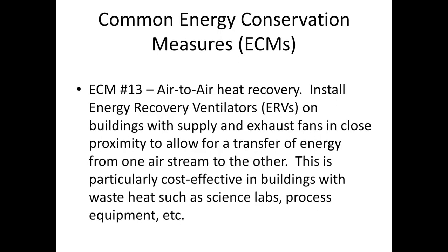So this is really installing energy recovery ventilators in a lot of climates, especially when it's very cold outside, but you have a lot of waste heat, such as from science classrooms or science labs that may have fume hoods and other high heat content exhaust fans. This allows that energy to transfer to the supply side and preheat air before it's mechanically heated.